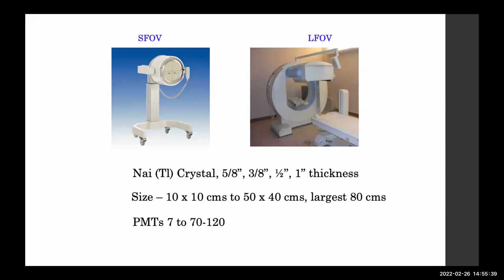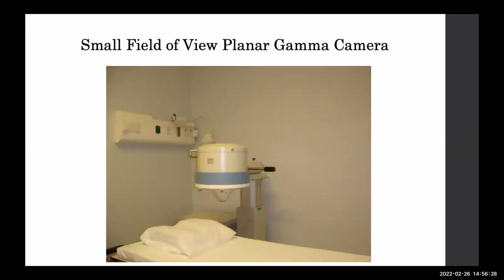Now, as far as gamma camera types are concerned, there could be a small field of view gamma camera, where you can see the total field of view is very small, 10 by 10 centimeters. The large field of view gamma camera has very large detectors, a large head, which can be 50 by 40 centimeters, and maybe the largest is around 80 centimeters. The crystal size can vary depending upon the use: 5/8 inch, 3/8 inch, with half inch or 1 inch thickness. Usually the 3 by 8 inch or 5 by 8 inch sodium iodide crystals are used. The photomultiplier tubes behind the crystals can be as few as 7, up to 70, and in some instances 120 in a large field of view gamma camera. So gamma cameras can be small field of view or large field of view.